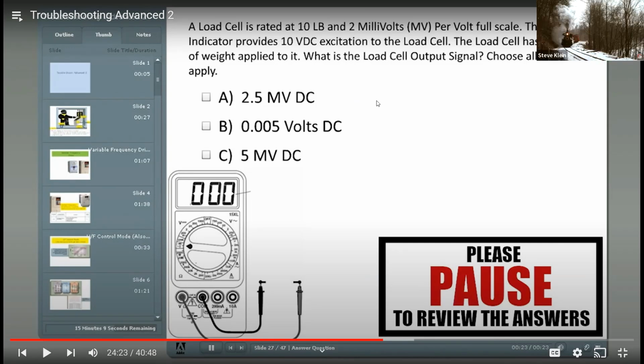We're going to go Canadian imperial gallons now. We've got an imperial gallon, which is 10 pounds. We're going to take half of that jug. Half that jug is going to weigh 5 pounds. Half of that half is a quarter, so it's going to weigh 2.5 pounds. That's how much weight we're putting on there. If the thing's all the way up at 2 millivolts per volt times the 10 volts, that's 20 millivolts. So half of the 20 is 10, and half of 10 is 5. Last I checked.